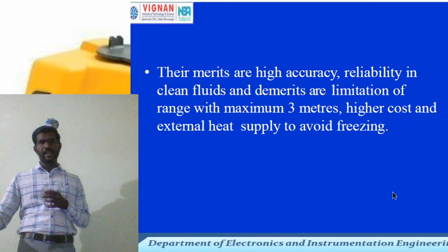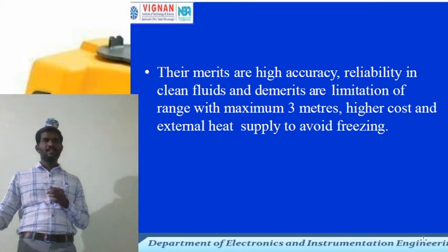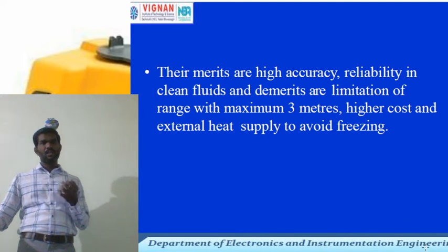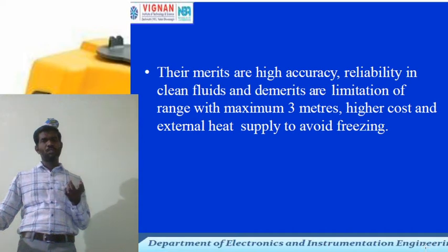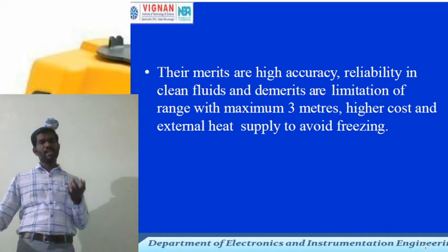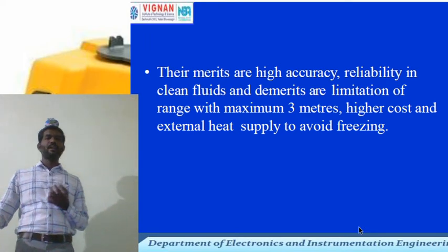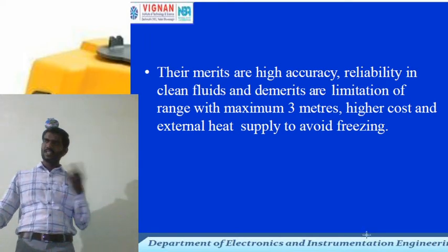Their merits or advantages are high accuracy and reliability in clean fluids. The demerits or limitations of this technique are that they can measure a maximum distance of only 3 meters, they are also high cost, and an external heat supply will be required to avoid freezing.